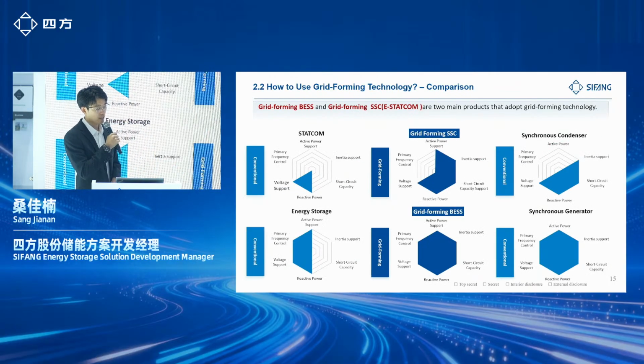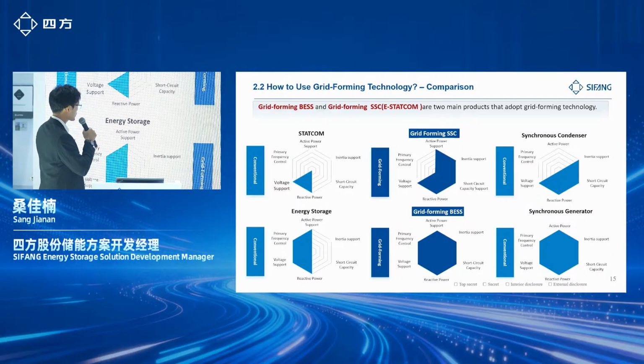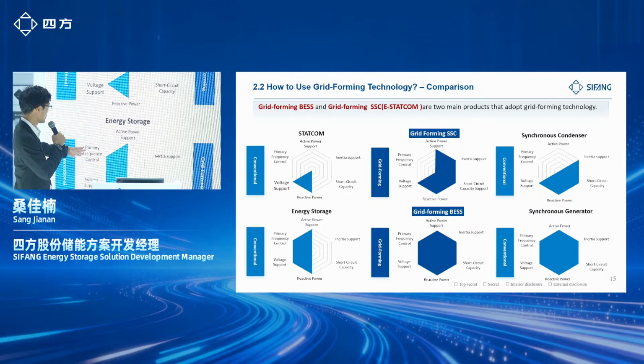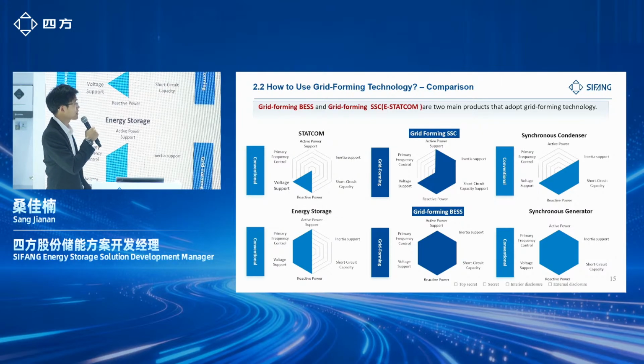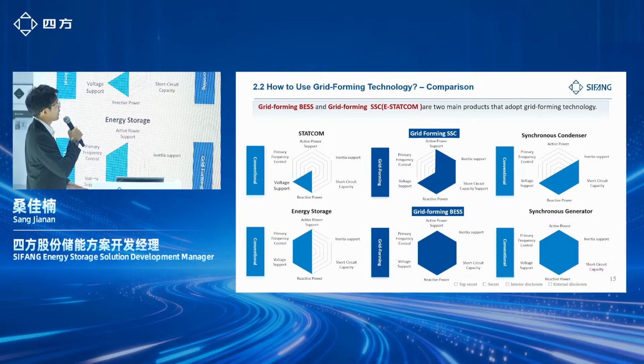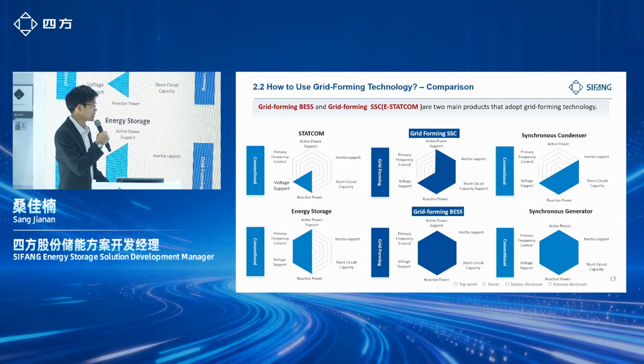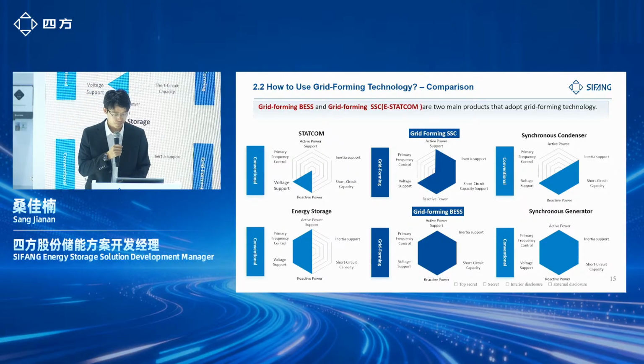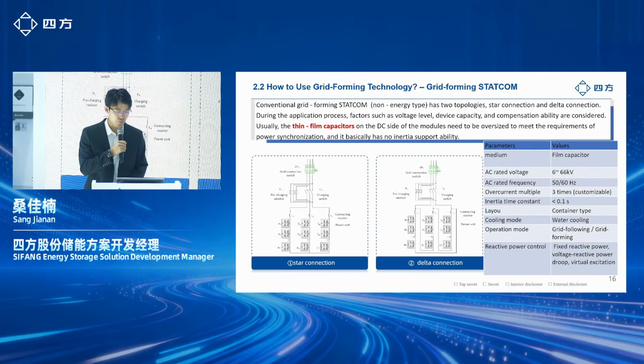We can see from here the comparison. From the left, you can see the conventional solution, the STATCOM. It cannot support inertial support and active power, right? It just outputs reactive power. And conventional energy storage, battery energy storage, cannot output inertia and short circuit capacity. But in the middle, we have Grid-Forming SSC. Grid-Forming SSC can output active power, reactive power, and inertia, right? And the Grid-Forming BESS can have all the functions, all-rounded, just like a synchronous generator.